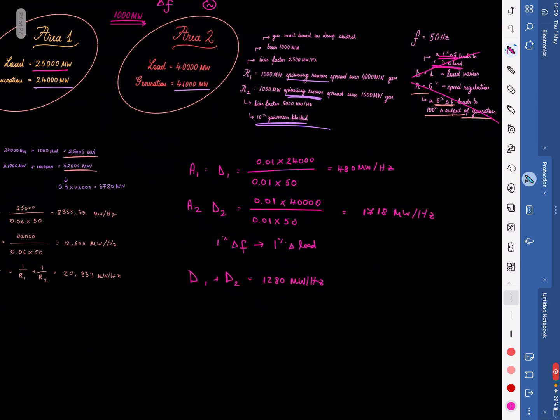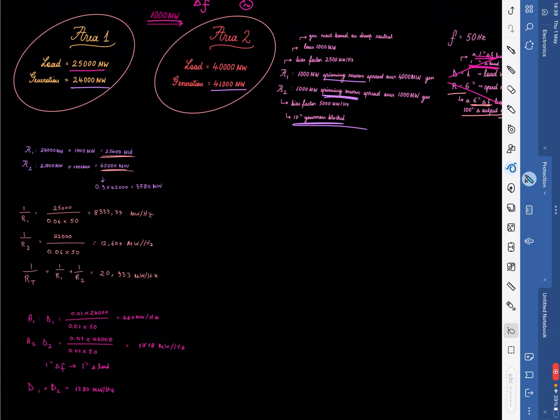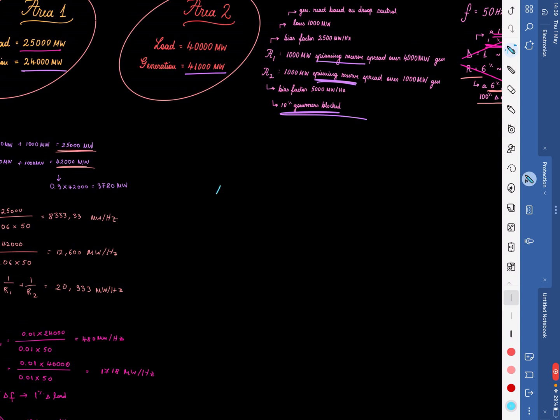What we are actually trying to calculate is the new frequency of the system. So let's calculate the change in frequency first. So the change in frequency will be the loss of load, so minus PL, divided by the droop response of the generators plus the damping of the load.